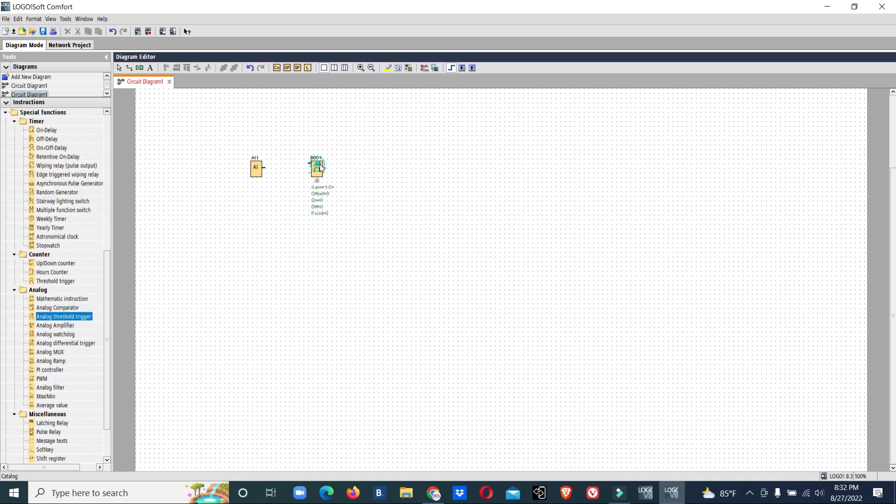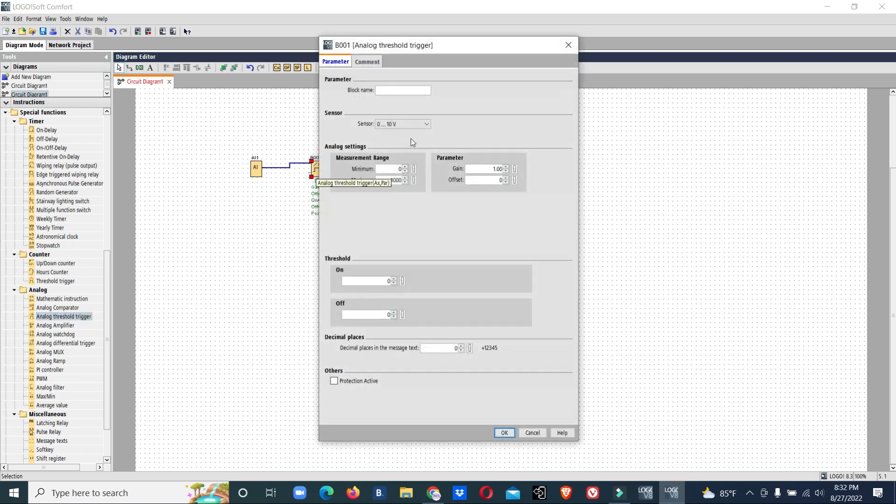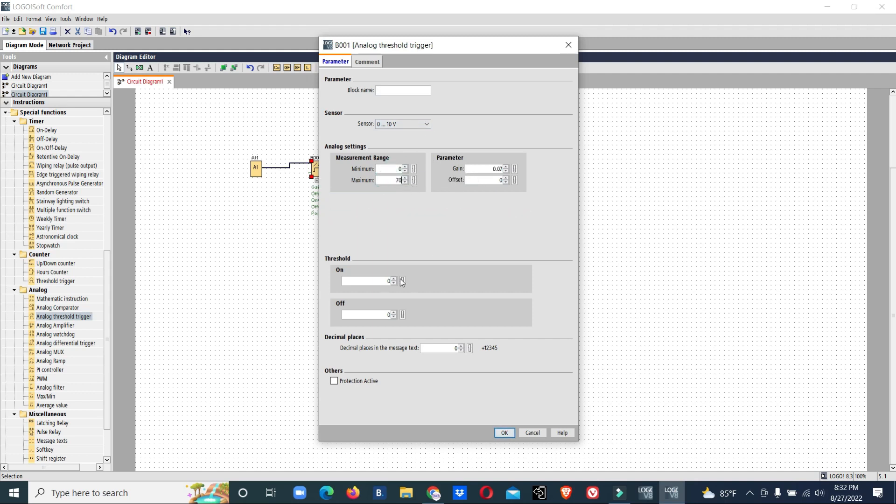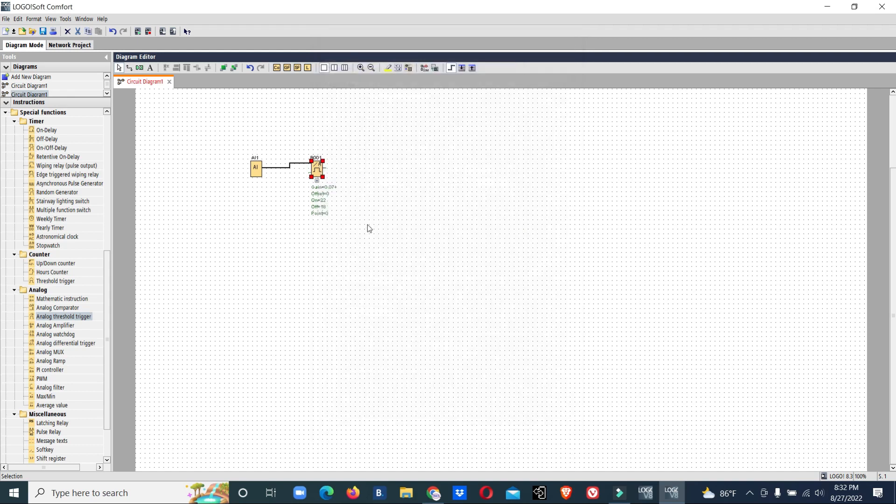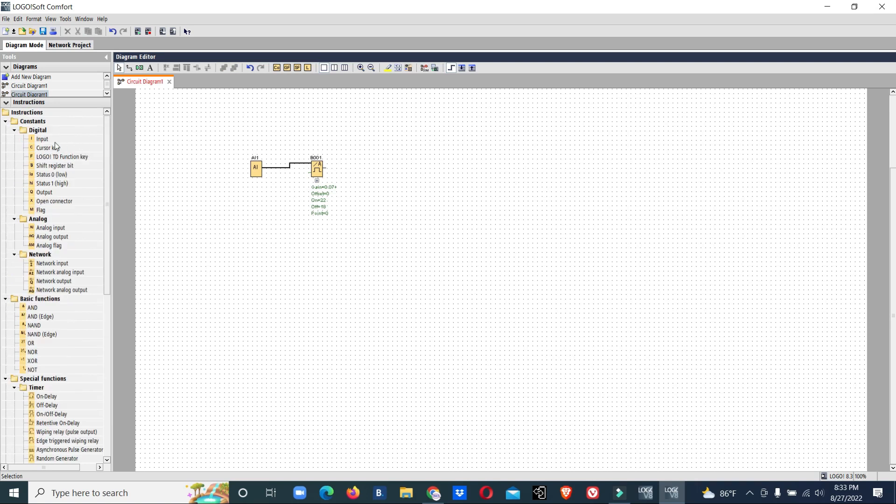Analog threshold. Now we will assign our temperature. Our sensor is 0 to 10 volt, as I told, 0 to 70 degrees Celsius. On will be 22 degrees Celsius, off will be 18 degrees Celsius. And we have one input, AHU running.